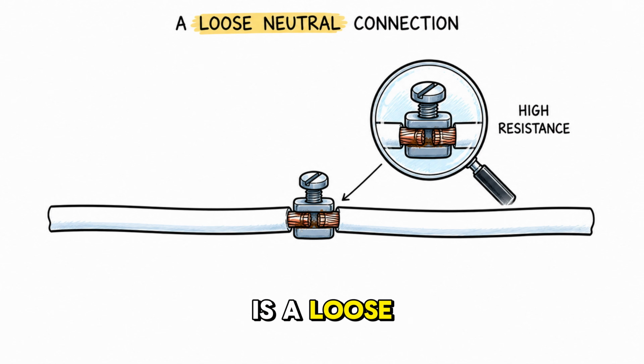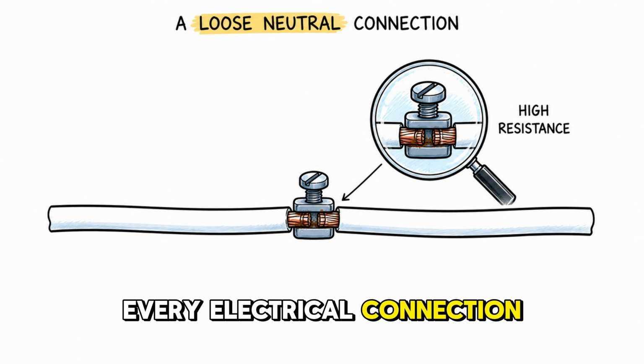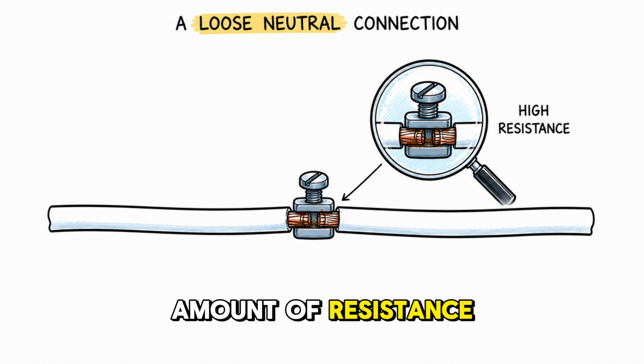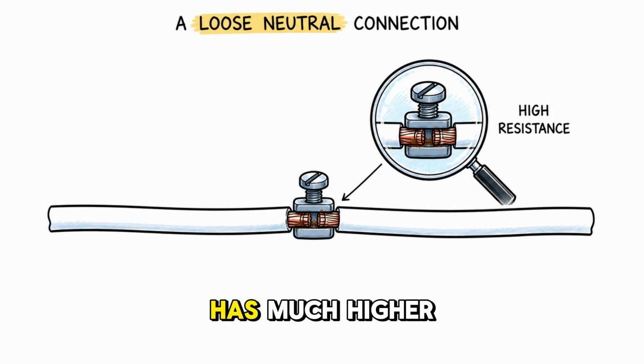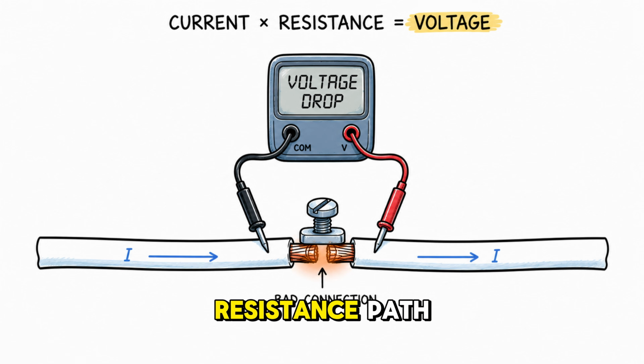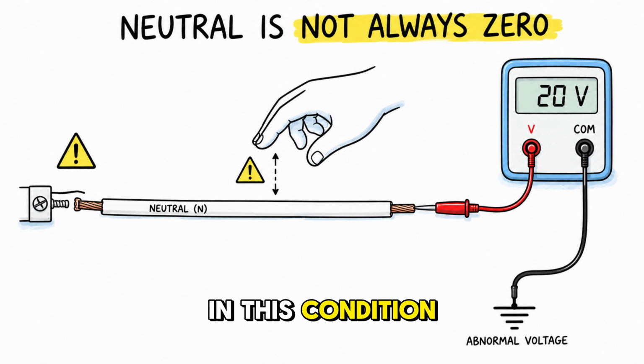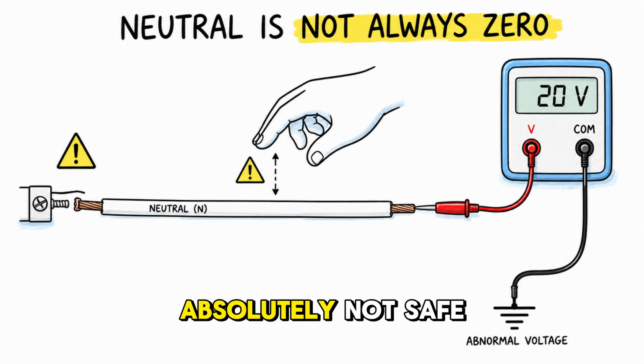The first condition is a loose neutral connection. Every electrical connection has a tiny amount of resistance. A loose or corroded neutral joint has much higher resistance than it should. When return current flows through this high resistance path, Ohm's law takes over. Current multiplied by resistance equals voltage. Because of that bad connection, a real and dangerous voltage drop is created across the joint. In this condition, your neutral wire is no longer at 0 volts. It rises to 10, 20, or even 30 volts above ground. Touching a neutral wire under these conditions is absolutely not safe.